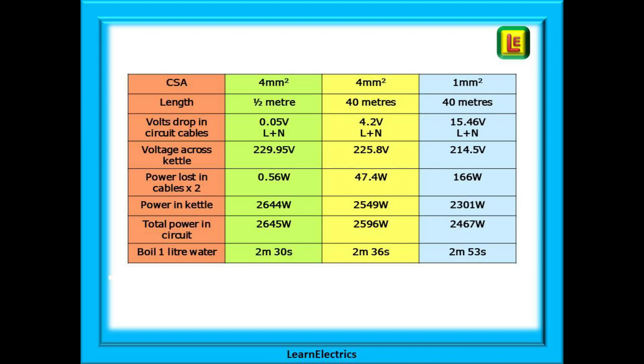This summary table shows the main observations across all three scenarios. The longer the circuit and the smaller the cable's cross-sectional area, the greater the voltage drop in the conductors. As cable resistance increases, the current that flows reduces. These factors combine to reduce the power output of the kettle. The final line compares the time to boil a liter of water — it may not seem significant, but over a year of usage the cost could be. All appliances — showers and cookers especially — will be affected, and lighting circuits may show a noticeable change in light intensity.